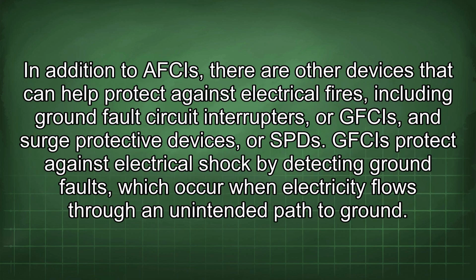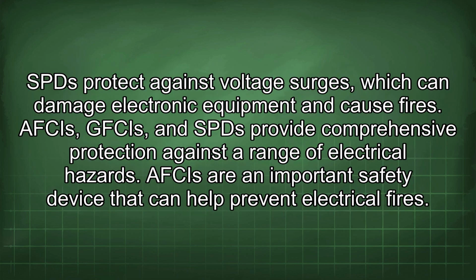In addition to AFCIs, there are other devices that can help protect against electrical fires, including ground fault circuit interrupters, or GFCIs, and surge protective devices, or SPDs. GFCIs protect against electrical shock by detecting ground faults, which occur when electricity flows through an unintended path to ground. SPDs protect against voltage surges, which can damage electronic equipment and cause fires. AFCIs, GFCIs, and SPDs provide comprehensive protection against a range of electrical hazards.